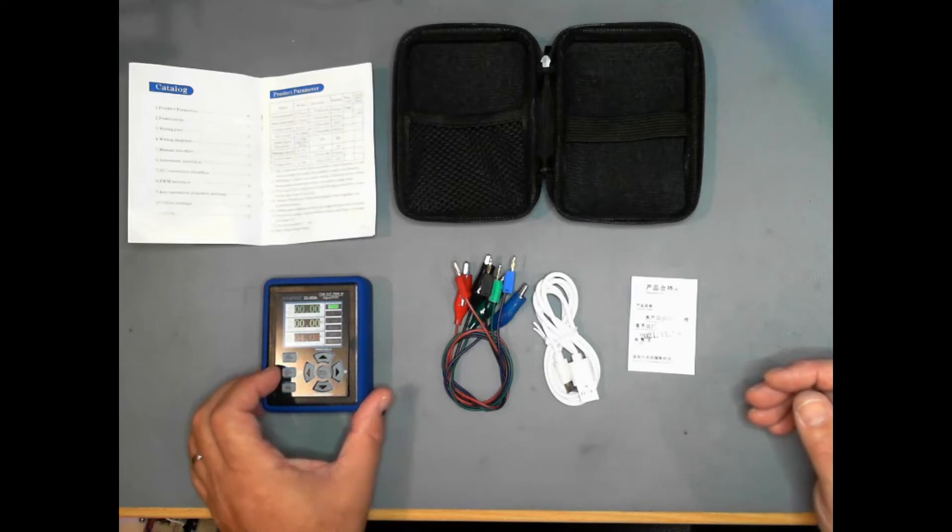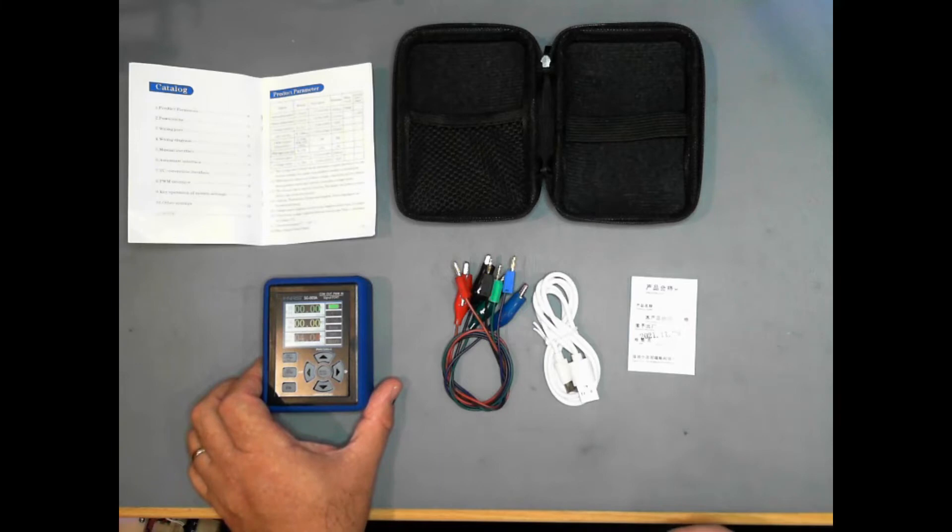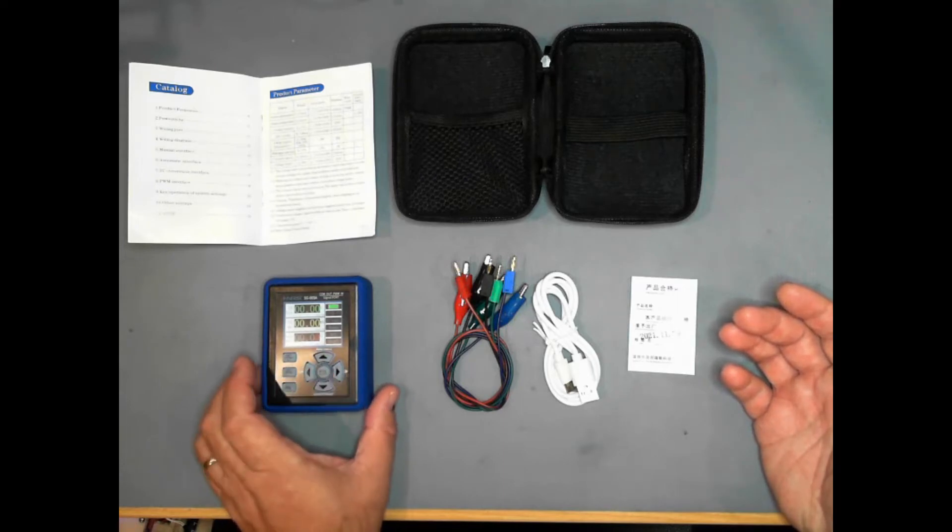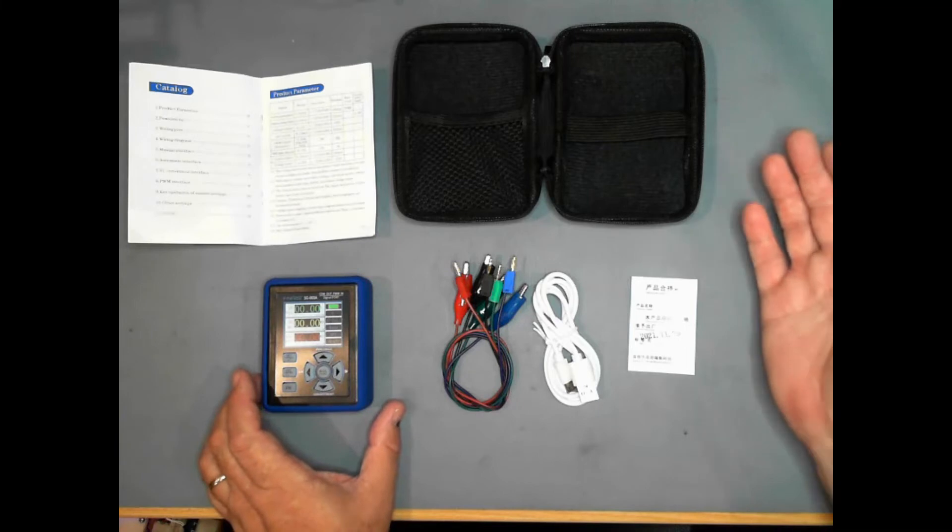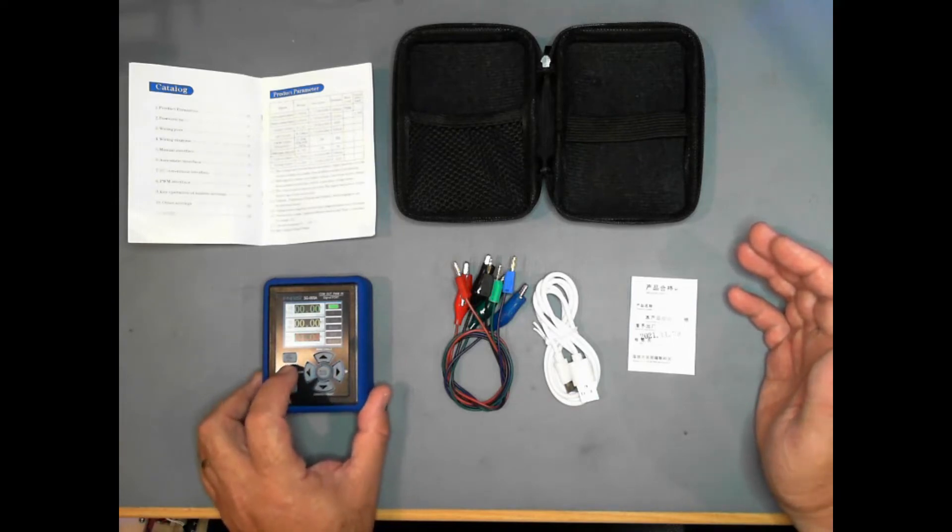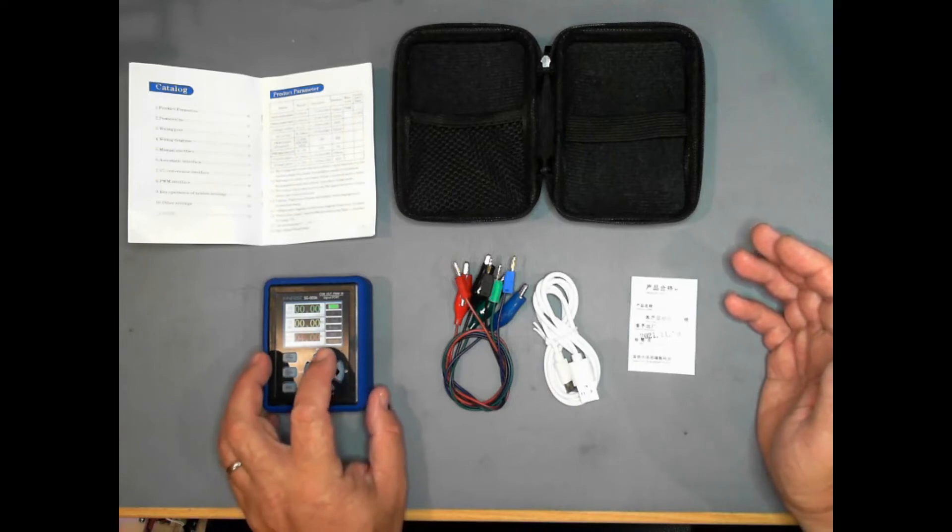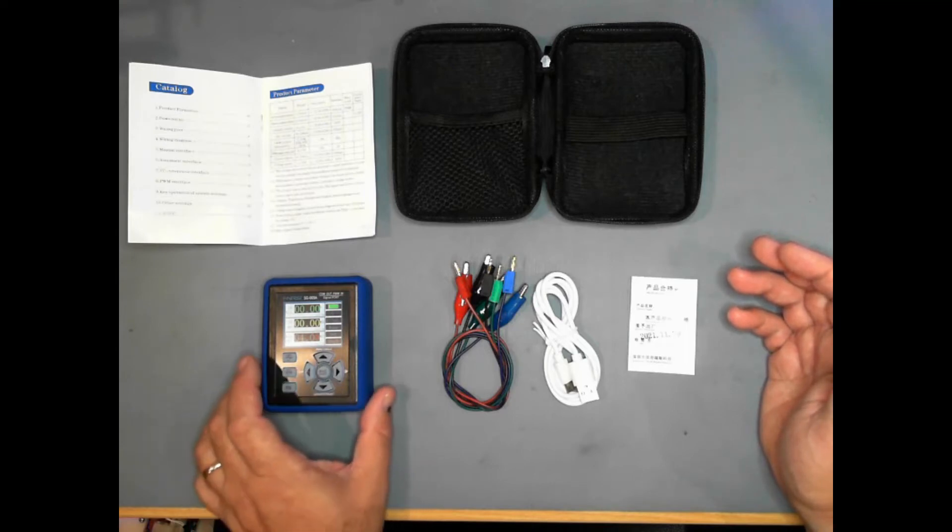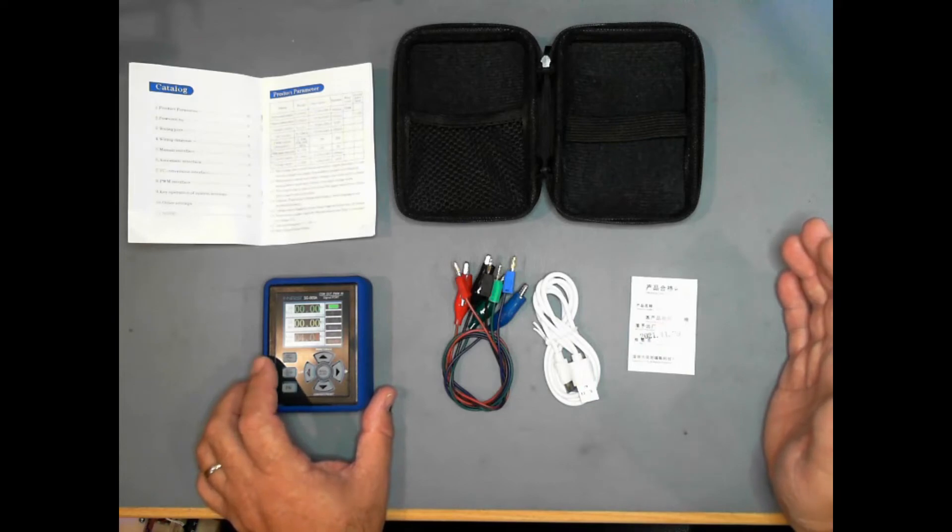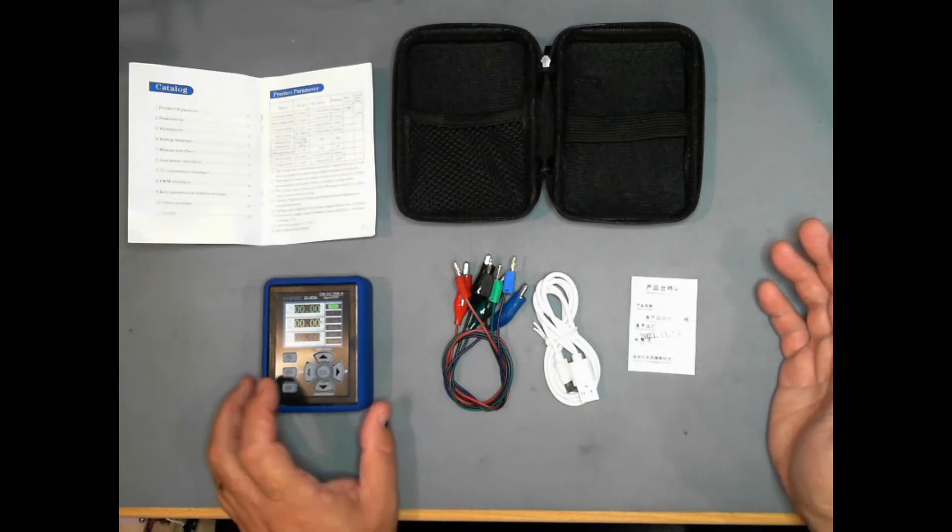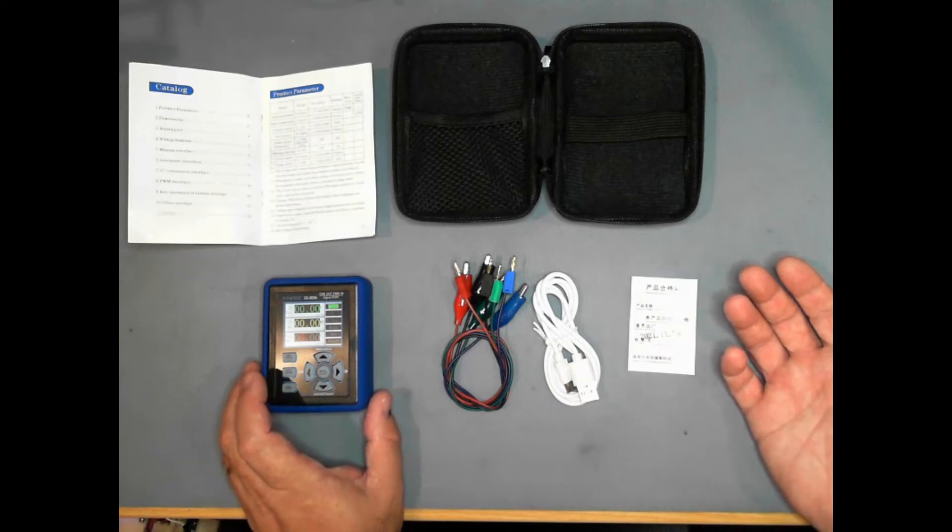It will show you a graph. This is a 4 to 20 milliamp mode where you can actually make it act as the load, so you can send a test signal into a controller. I think that one is a voltage output, and this is a 24 volt out, so we can actually send out a voltage or we can send that 24 volt. This is our 4 to 20 milliamp. We can actually adjust how many milliamps it will allow to pass through for our testing. This is all controlled by this ESC out button. The manual is not very clear on its operation.